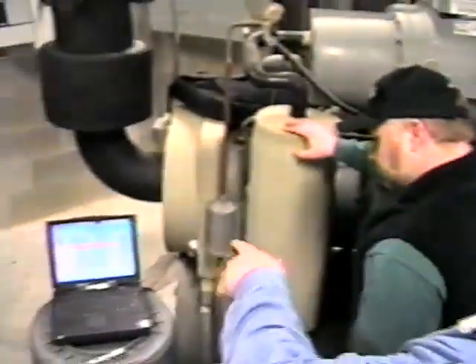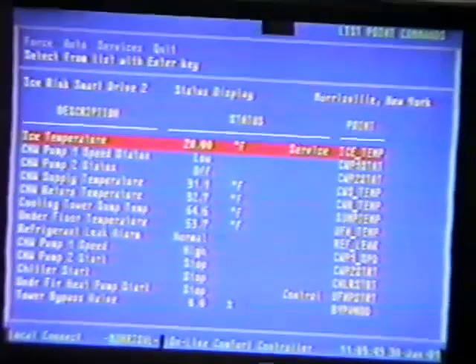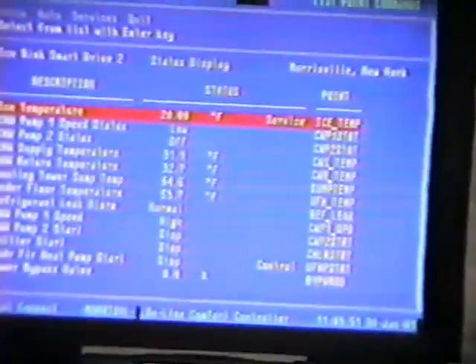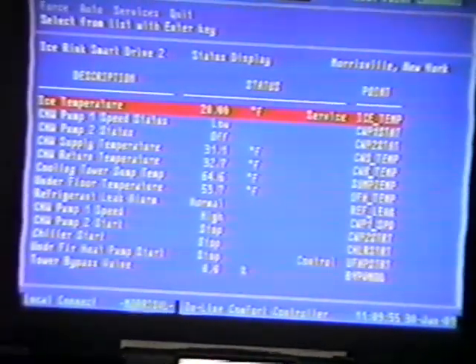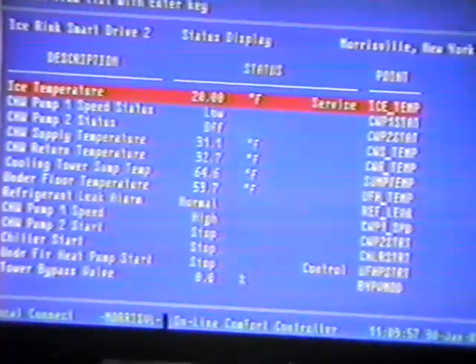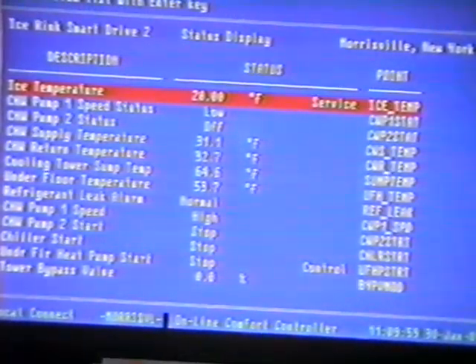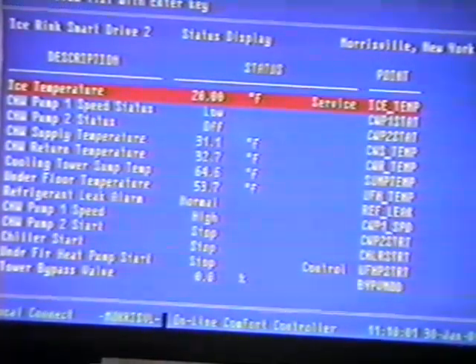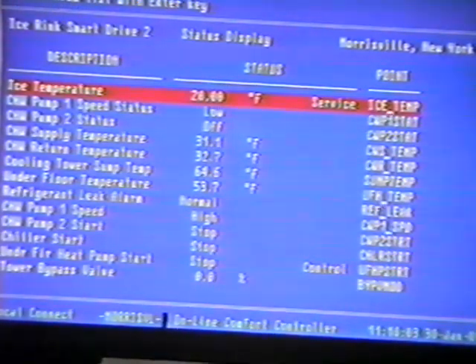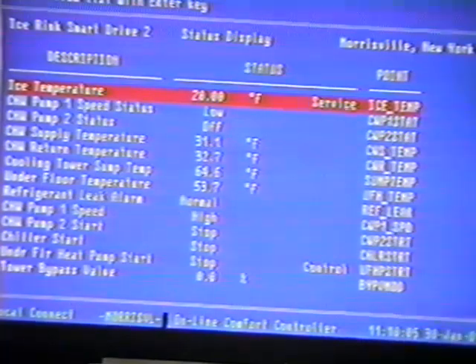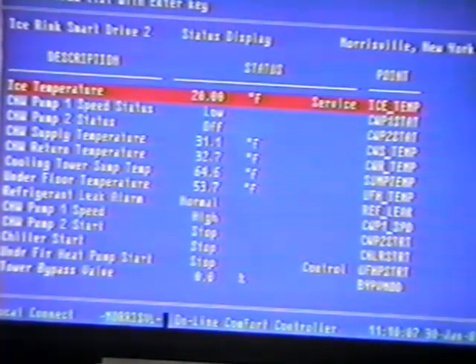So all we're doing then with that theory is, right now we're looking at the ice surface temperature, and we're going to control, right now we're set up for 21 degrees. I've got a 2 degree dead band on it, so you basically pull down to 19 before it shuts off, and at 21 it's back on again.